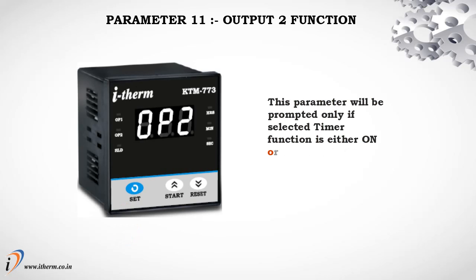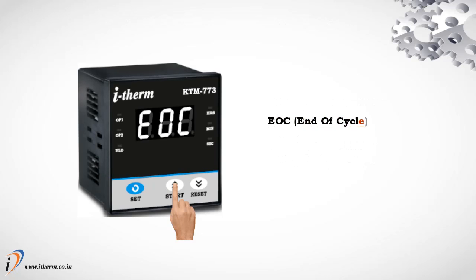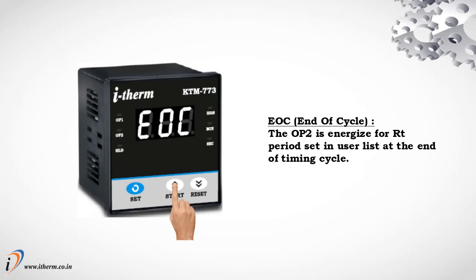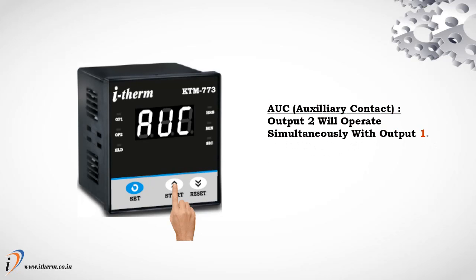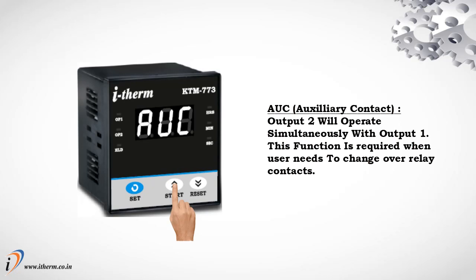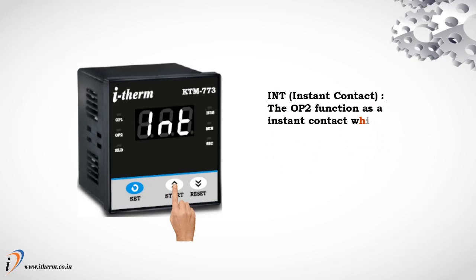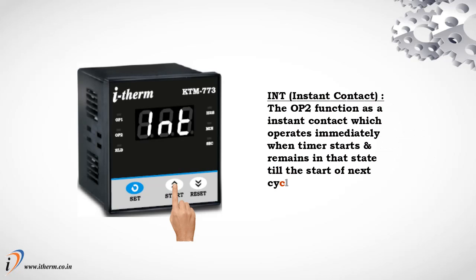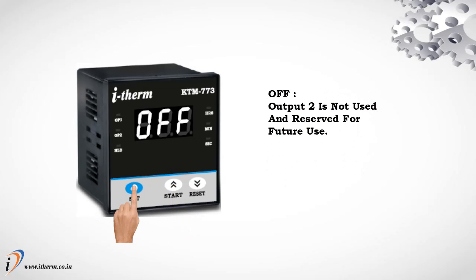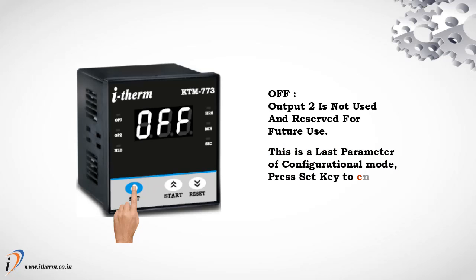Parameter 11: Output 2 function. This parameter will be prompted only if the selected timer function is either on delay or off delay — not applicable for cyclic modes. End of cycle: output 2 is energized for the RT period set in the user list at the end of the timing cycle. Auxiliary Contact: output 2 will operate simultaneously with output 1; this function is required when the user needs changeover relay contacts. Instant Contact: output 2 functions as an instant contact which operates immediately when the timer starts and remains in that state till the start of the next cycle. Off: output 2 is not used and is reserved for future use. This is the last parameter of configuration mode. Press the set key to enter run mode.